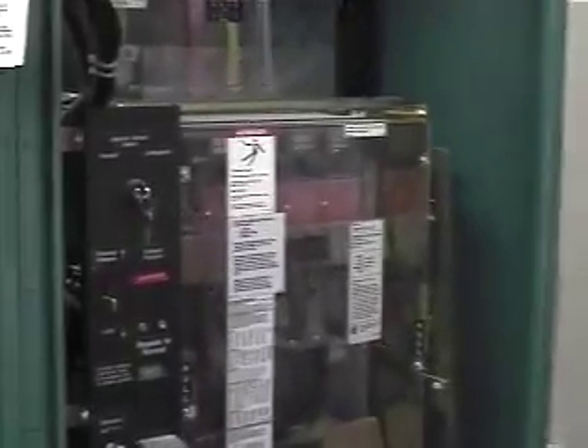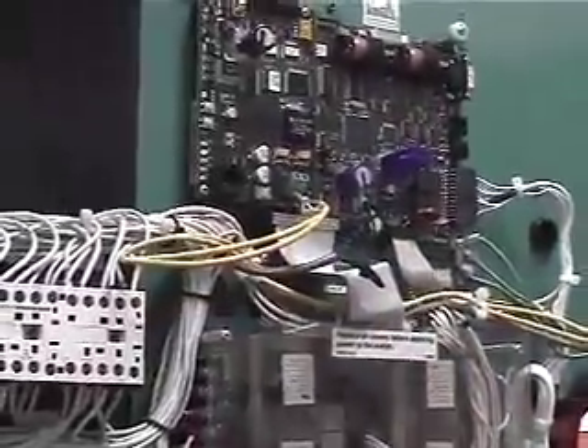Transfer switches, we're tied into these, communicating with them through the LAN. We're tied in right here, onto the LAN board there. Is there an enable or override for the generator, or just monitoring? There's the possibility of it, but we haven't wired it up directly. No, it automatically gets a signal. The generator communicates with the transfer switches through the LAN back and forth themselves as well, and then we monitor stuff with that same connection. We can't turn it on at this moment. No, it's just a matter of linking up a couple of objects, and we could.